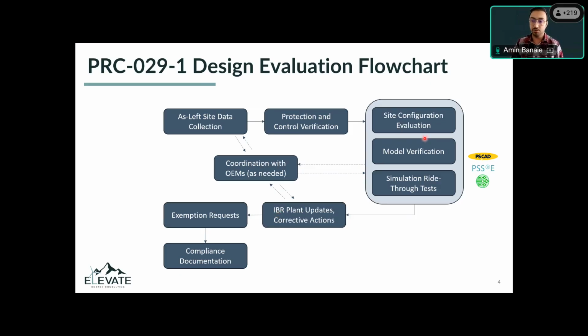And then we're going to get to the stage of evaluation for the site configuration, do a quick model sanity check, and then start running simulations. We have around 8 to 10 simulation cases that we run for PRC-29. And then once those simulation results are analyzed, we're going to come up with if any update is needed in the plant, or what corrective actions can be taken to address those non-compliant items. And then help the client with filing for exemption requests if there is any hardware limitation, and also help them put together a compliance documentation package that can be submitted to NERC.